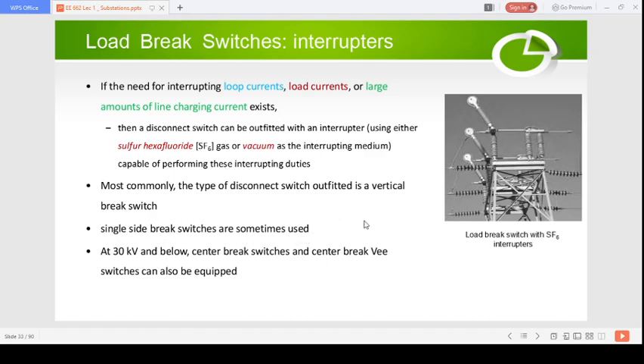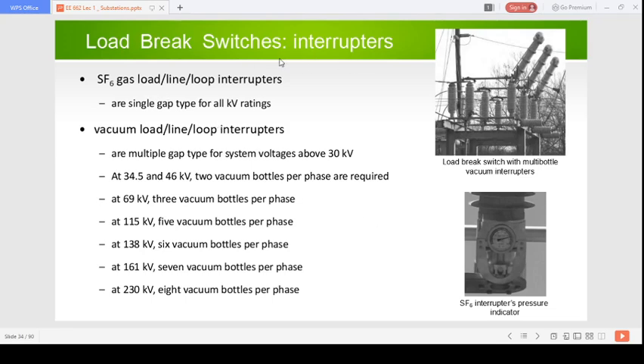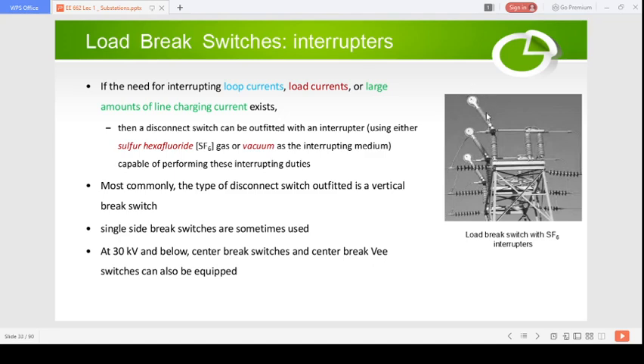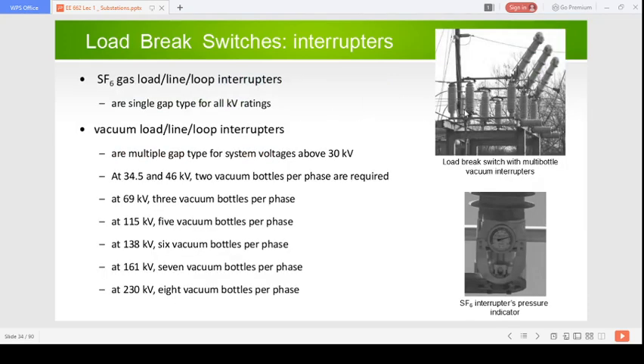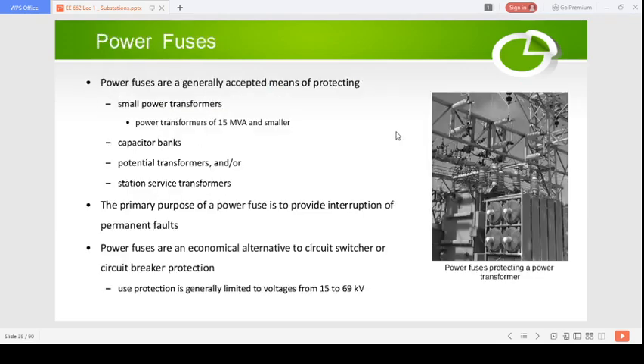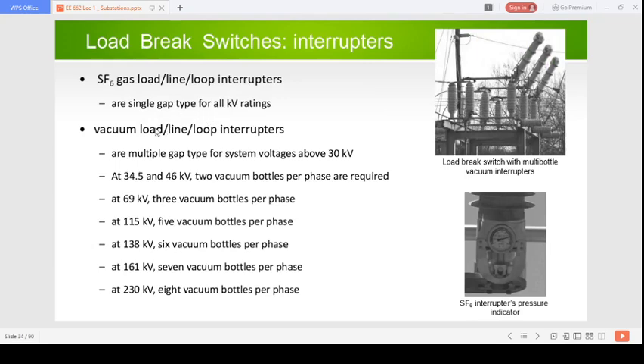Okay, let's see the different types of load breaking switches. You have the load breaking switches with SF6 gas, the load line or loop interrupters. They are a single gap type for all kV ratings. So you have only one gap type for all kV, and it will look something like that. Inside this arrangement you have this interrupter with SF6 gas. Later we will see how it typically happens. And then the vacuum load line or loop interrupters.